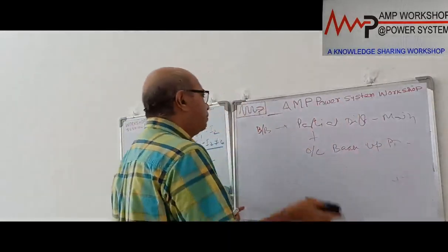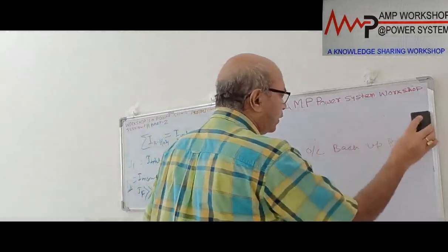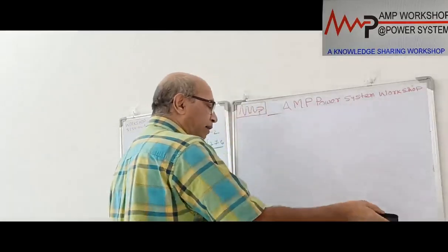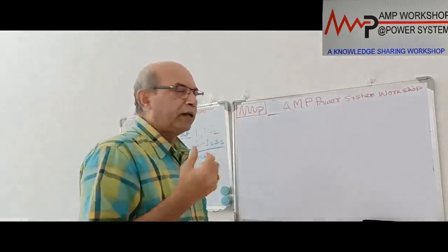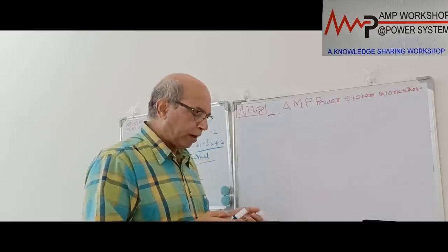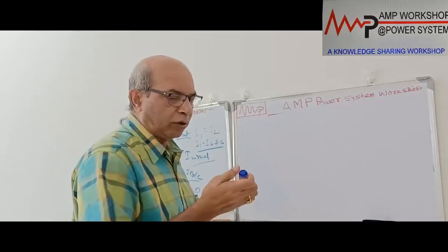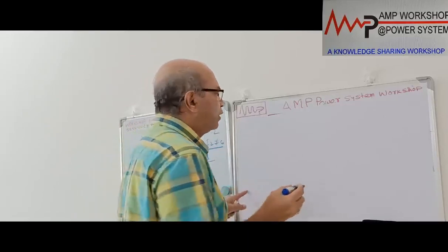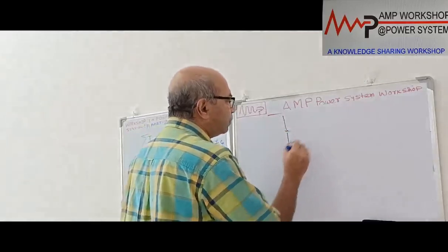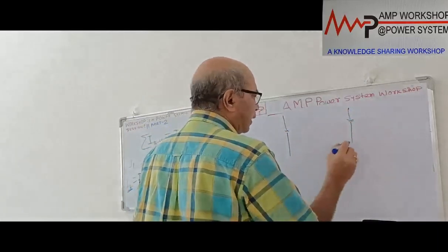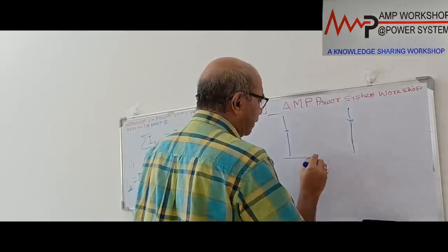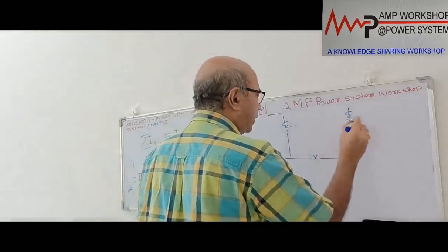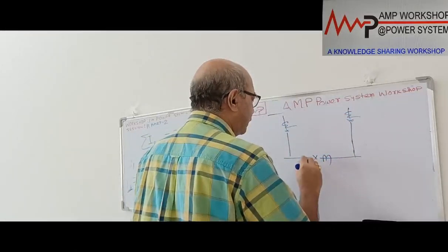Now, when the switchboard is above 11 kV, from 15 kV onward, we have to consider differential protection for the bus bar. We have the differential protection as three schemes, and one is the conventional circulating current differential scheme. How it is made, I am drawing again the single line. Suppose this is one switchboard. There is a CT over here, a CT over here, and a CT over here.